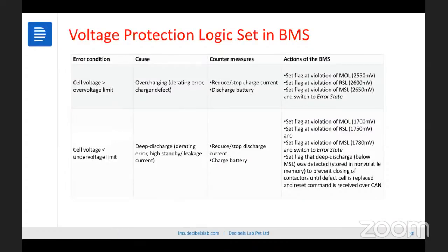So there are some protection logics. Don't go by these values exactly, but let's say a flagging error condition: cell voltage is greater than the over voltage limit. This is the algorithm approach, how we write logical algorithms, like state machines. So if you talk about voltage, there's an over voltage limit and an under voltage limit. Let's talk about how we actually define it.